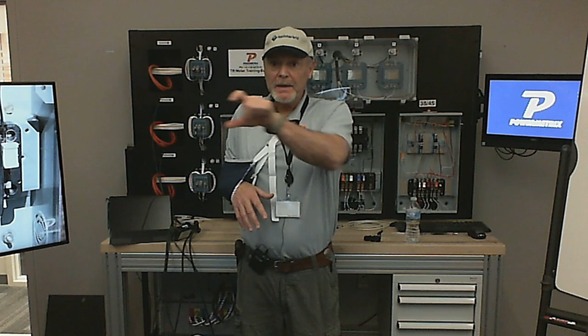I'm wired up on all three phases for voltage, A, B, and C, but on currents I have no connection on B phase, so that's 3 voltages and 2 currents. This matters later when picking your service type on the machine, since that's distinguished by the number of voltages and currents. That's why it's important to assess this correctly, because you could pick a 5S delta on the machine that shows 2 voltages and 2 currents, and that's not what you want. I've got 3 voltages here, so you need to pick the option with 3 voltages and 2 currents.